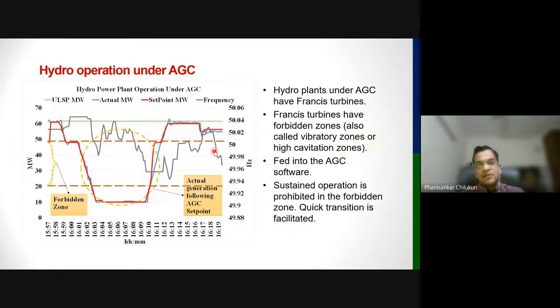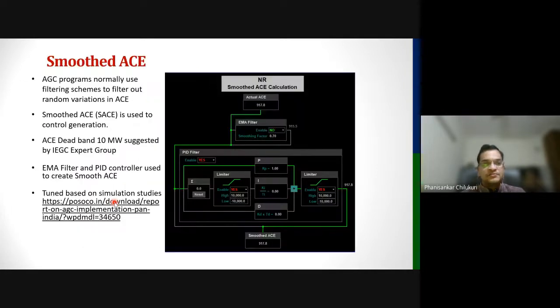Hydro power plants are also there. Hydro power plants under AGC, they have Francis turbines in India. Several hydro power plants. The Francis turbines have forbidden zones. They are also called as vibratory zones or high cavitation zones. They are fed into the AGC software, those zones, and sustained operation is prohibited in that forbidden zone. And we facilitate quick transition through that forbidden zone.